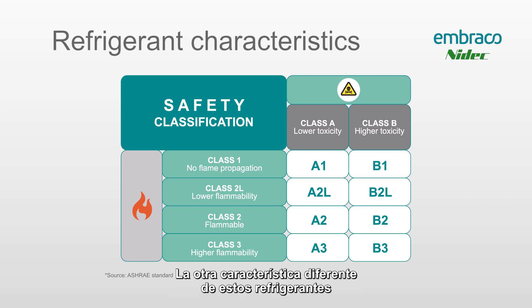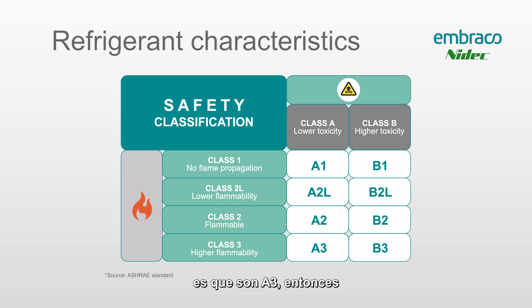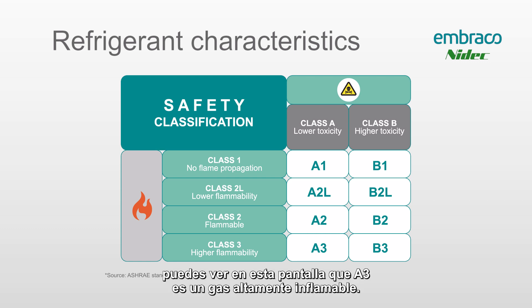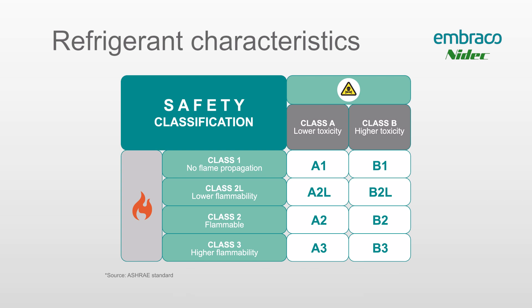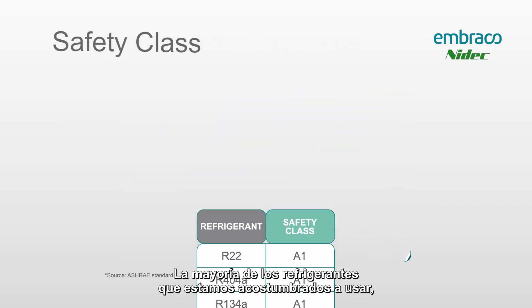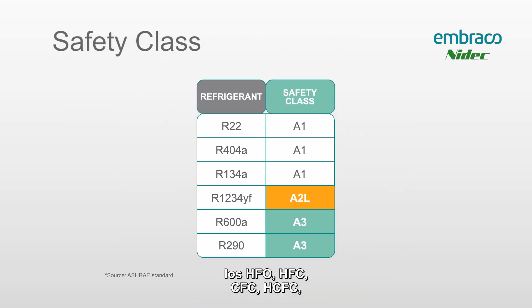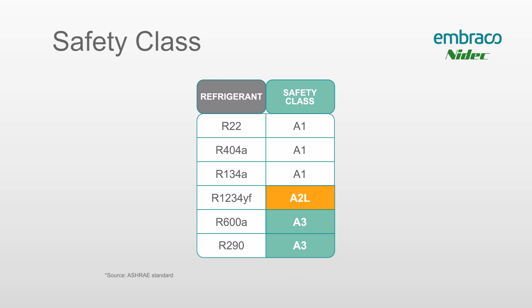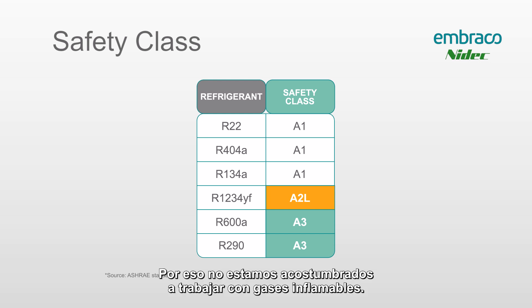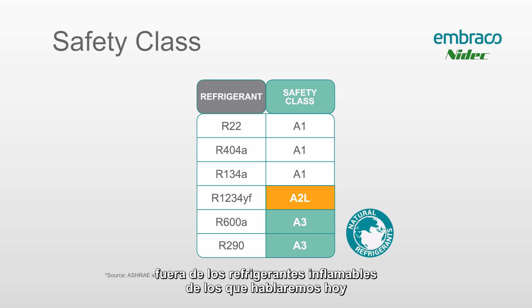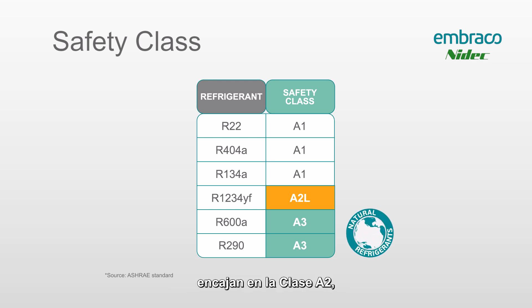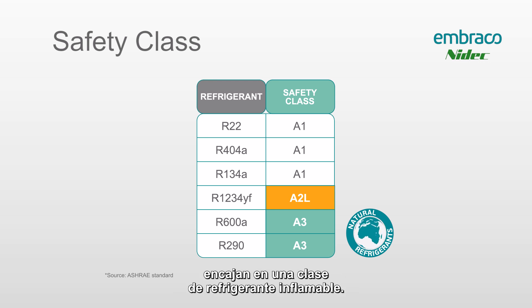The other thing that's different about these refrigerants is that they're A3. You can see on the screen that A3 is a highly flammable gas. Most of the refrigerants that you're used to using — the HFOs, HFCs, CFCs, HCFCs — all of these are A1 gases, so we're not used to working with flammable refrigerants. Some of the new gases outside of the flammable refrigerants we'll talk about today fit into the A2L class, but either way, all the new refrigerants fit into a class of flammable refrigerant.